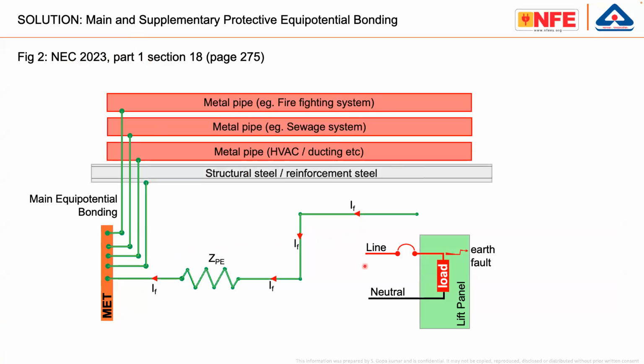You can see here the lift panel. The body of the lift panel has to be connected to a common bus bar. The common bus bar must go from the lift room to the main earth bus bar of the main distribution board. And in the lift room, all the exposed metal parts also must be connected to the MET, sub-MET. This is called supplementary equipotential bonding. You can find the picture and the explanations in NEC 2023 Part 1 Section 18, page number 275.